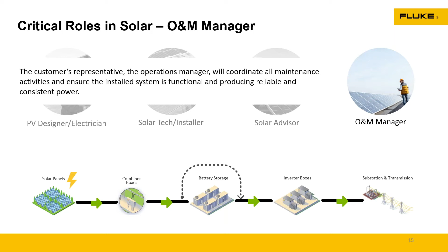So with that, you have all the components in the solar system and the different individuals working in that environment. There's a lot going on, a ton of wiring connections and terminations that need to be checked for corrosion, looseness, or water damage, since these are out in an environment where water can affect the wiring. Wire management is huge here. Imagine those actuators spinning and rotating; if you get a pinched wire, you've caused a ground fault and shorted out the system, losing the capacity and load you need.